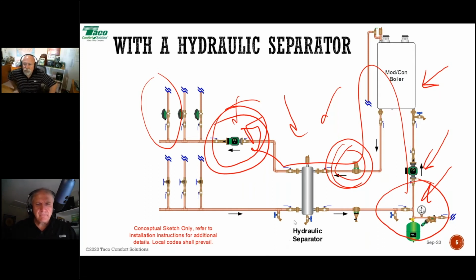Chris has got one. Do circ pumps go on the supply side or return side? I've seen both. Well, I think what you're referring to is side of the boiler. So again, you'll hear me reiterate this later, but just follow what the manufacturer shows you in their book. They'll show you when they want to pump away from their boiler, and they'll show you if they want to pump in. As John elaborated on, there's a lot of time nowadays they specifically want you to pump into the boiler. Not in every case, but again, the manufacturer is the one that has to stand behind everything. So do it as their drawing shows you.